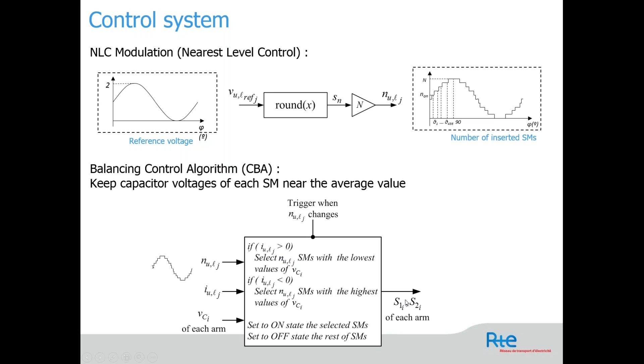So the protection used, now the protection is very simple. Of course, in the real world it should be much more complicated, but here we keep it simple since it is a benchmark. The main two controls are one from the AC side and one from the DC side. We measure the AC voltage at the primary side and the PCC, and we check if it's lower than 0.1 per unit, then we block the converter. Otherwise, the converter will manage the fault. So this protection is for three-phase fault.